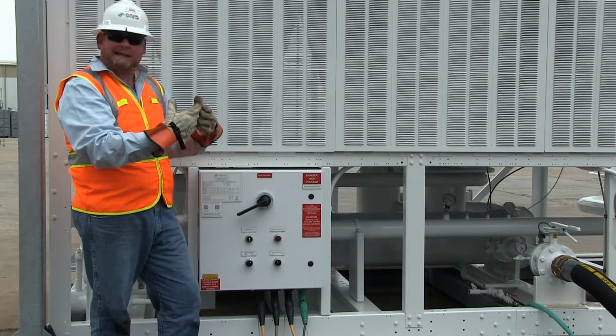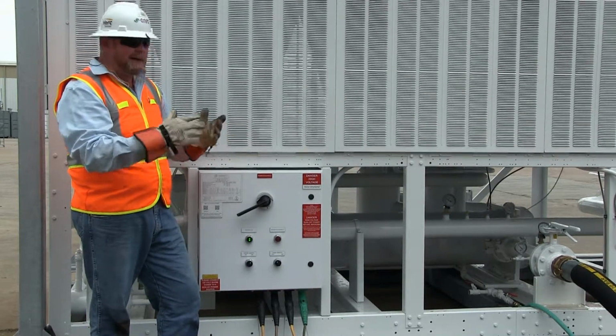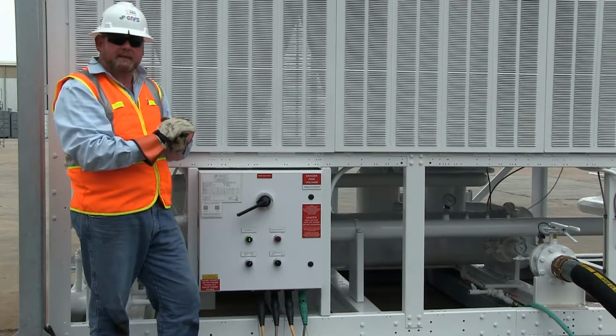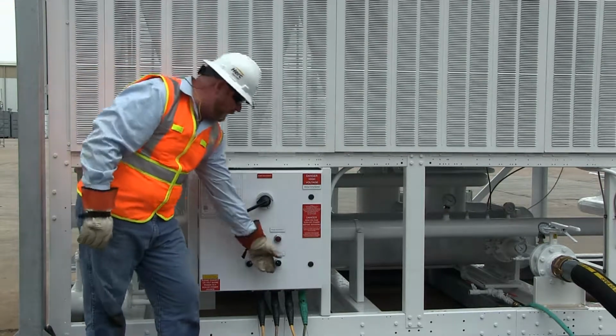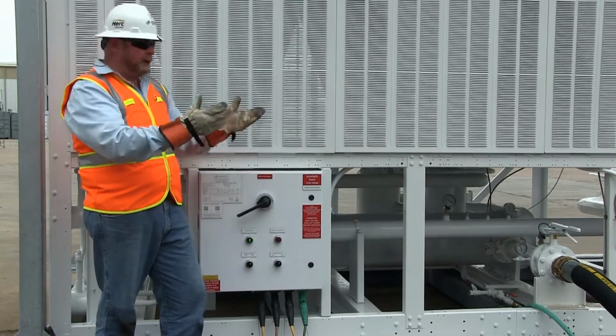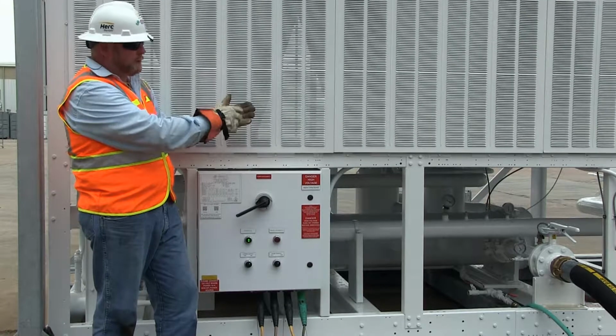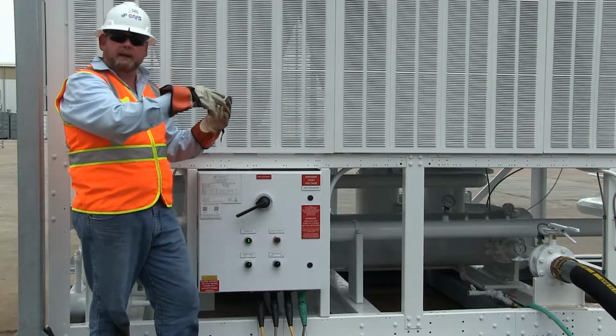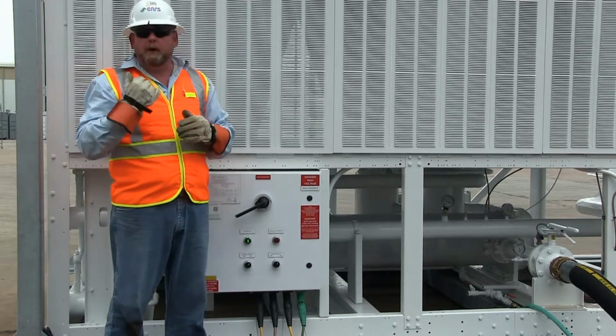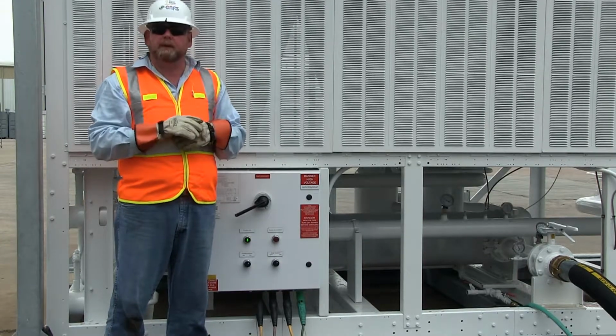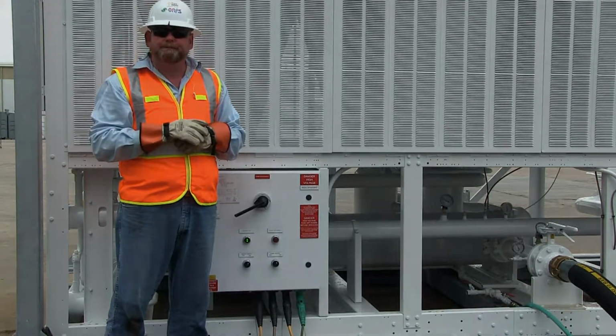We've done that process about 3 or 4 times and have gotten all the air out of the system, or most of it out of the system. So we're ready to leave the pump on and running, and it's circulating through our chiller, heat exchanger, through our pump, through our air handling unit. Now our next step is going to be to go to the control panel and actually start the chiller up and start making cold water.